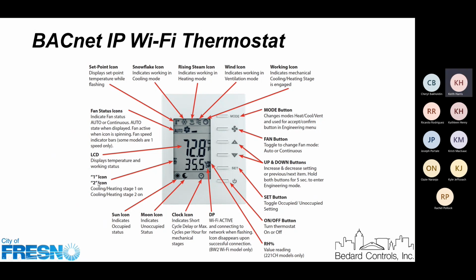The 1 and 2 icons refer to how many stages of cooling and heating. In most cases, we only have one stage of cooling and one of heating. Some of the larger units have 2 of cooling. If it's available, we hook it up, but most of the smaller package units only have 1 of each. And then this center display is the actual temperature, and we have it read in Fahrenheit. So it should read somewhere around 70 degrees, 72, 74 on a regular basis.